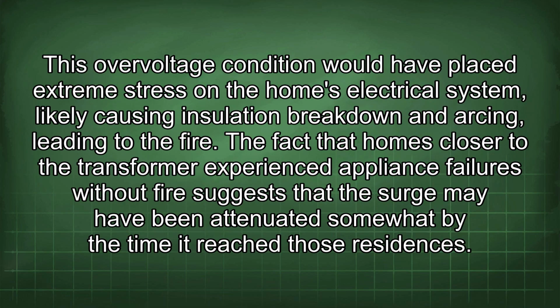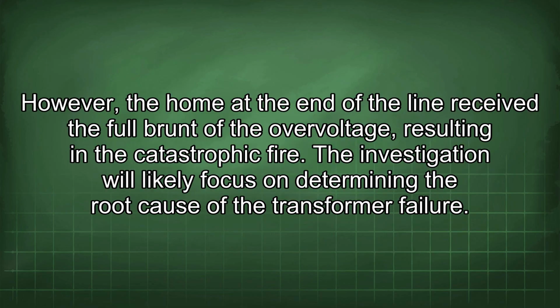This overvoltage condition would have placed extreme stress on the home's electrical system, likely causing insulation breakdown and arcing, leading to the fire. The fact that homes closer to the transformer experienced appliance failures without fire suggests that the surge may have been attenuated somewhat by the time it reached those residences. However, the home at the end of the line received the full brunt of the overvoltage, resulting in the catastrophic fire. The investigation will likely focus on determining the root cause of the transformer failure.